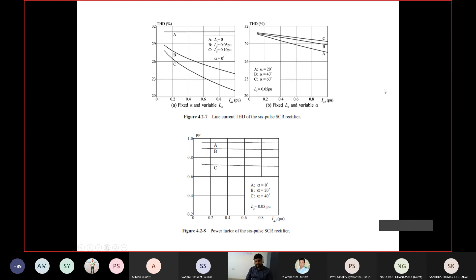These graphs all show the THD factor only, and one main thing we want is the SCR controlled rectifier controlling the DC side voltage based on the firing angle. The source current has the problem of injecting harmonics, so that's why it is a bit avoided. But can we interface a renewable energy source to a grid through an SCR controlled rectifier? Yes, we can. How? By connecting your renewable energy source on the DC side and operating the SCR controlled rectifier in the regenerative mode of operation. Then it is possible to inject the current from DC to AC side, that means injecting power from the renewable energy source to the grid.